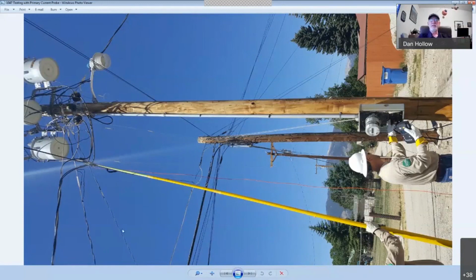In quite a few cases, you find utilities that don't have their CTs mounted in cabinets on the ground somewhere in close proximity to the meter socket with the test switches. You have the CTs mounted up on a bracket. If you look just underneath those transformers on that pole, right by that street light, you'll see 3 CTs mounted on a bracket. When you have that situation, you have to use a high voltage probe or a light wire probe that has a fiber optic cable. That orange cable coming down is fiber optic, and then it goes to a module on the ground. It in turn connects to the CT tester that's being used by the gentleman there in front of the meter socket.